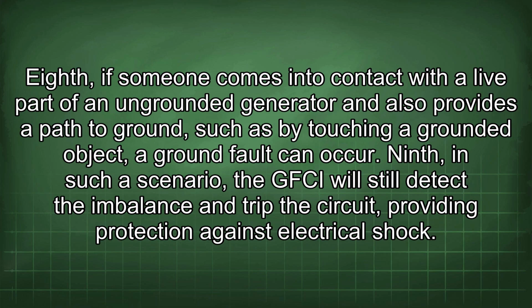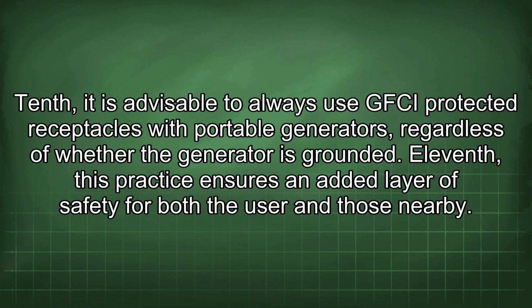Ninth, in such a scenario, the GFCI will still detect the imbalance and trip the circuit, providing protection against electrical shock. 10th, it is advisable to always use GFCI protected receptacles with portable generators, regardless of whether the generator is grounded. 11th, this practice ensures an added layer of safety for both the user and those nearby.